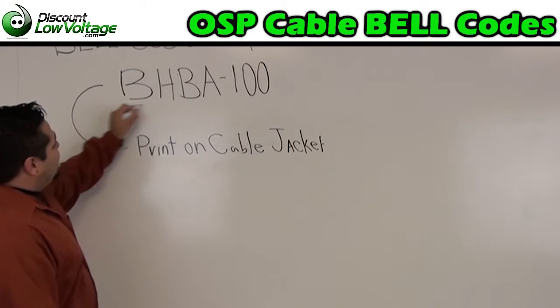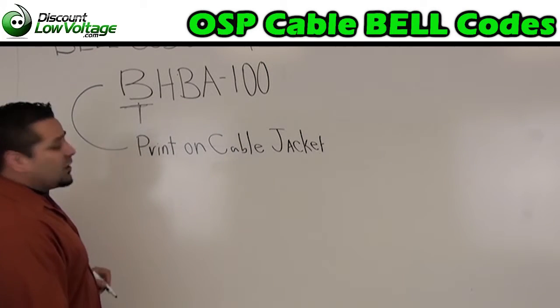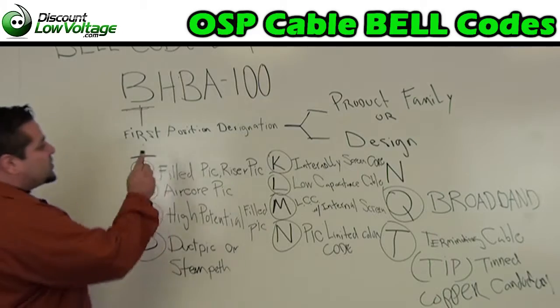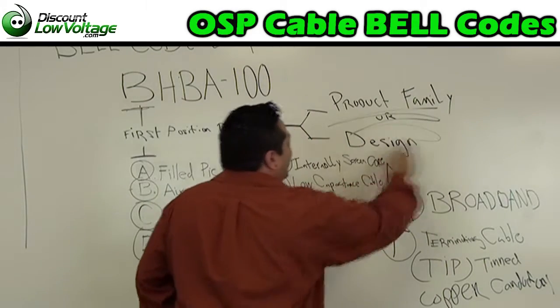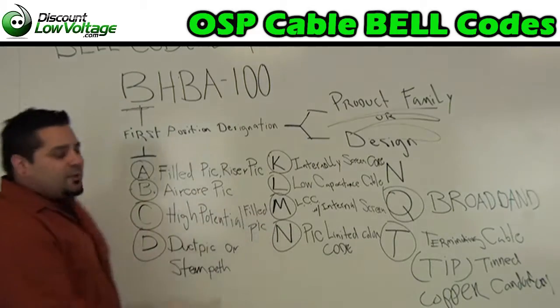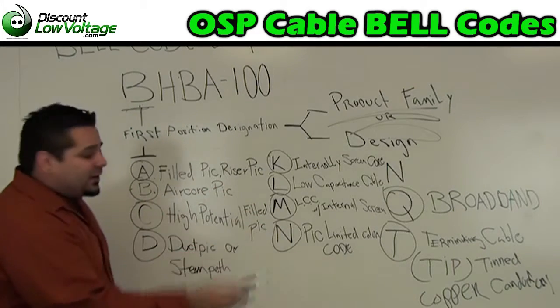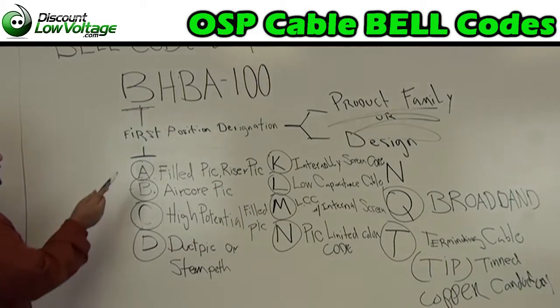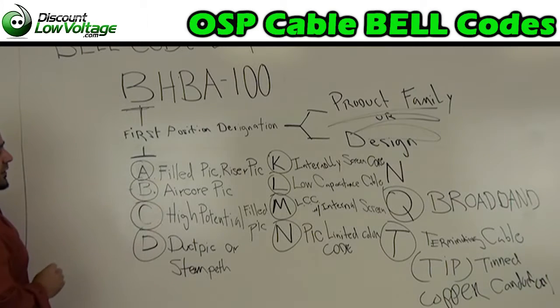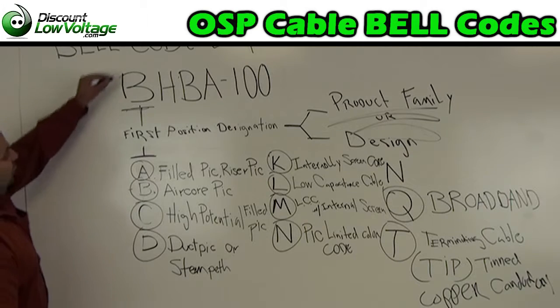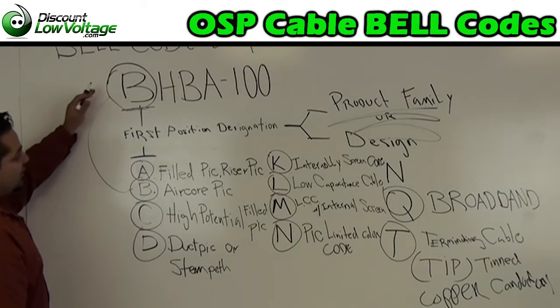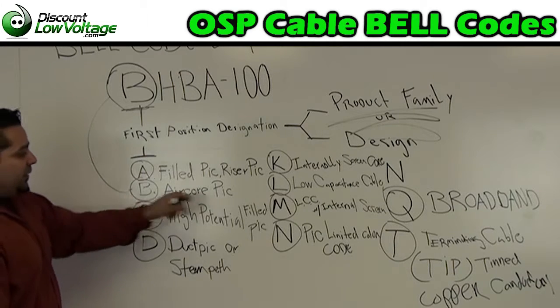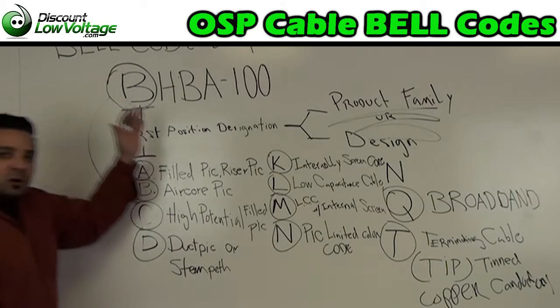Let's figure out what the first position means. The first position designation stands for either the product family or design of your cable. You have A, which is a filled PIC riser PIC cable. B, an air core PIC. Our first letter here is a B, so this is telling us we have an air core PIC to start off our part number.